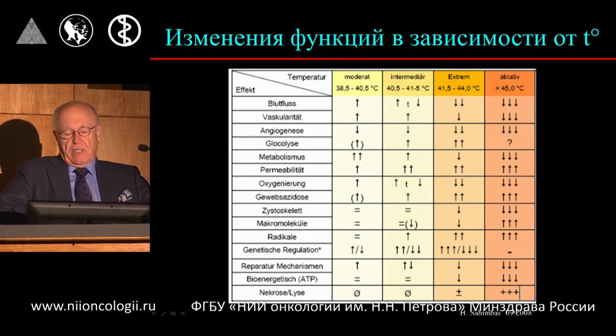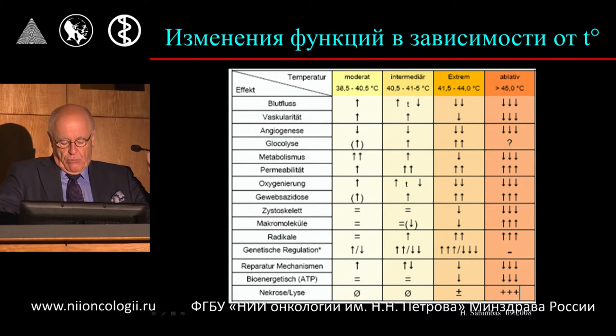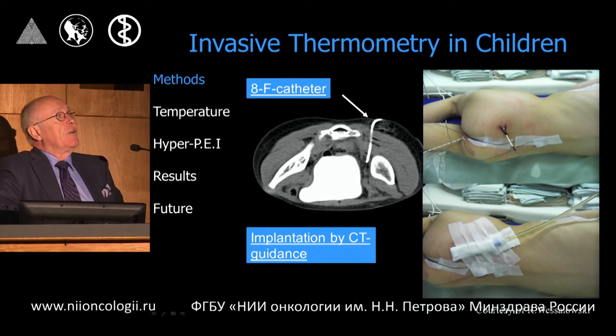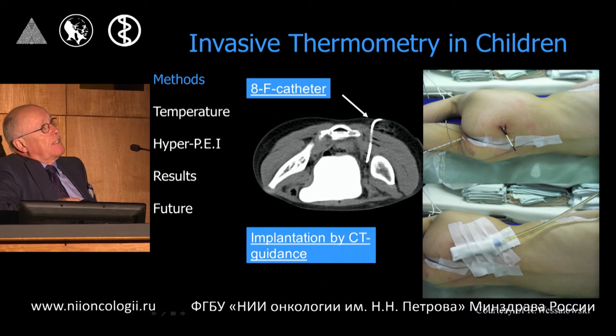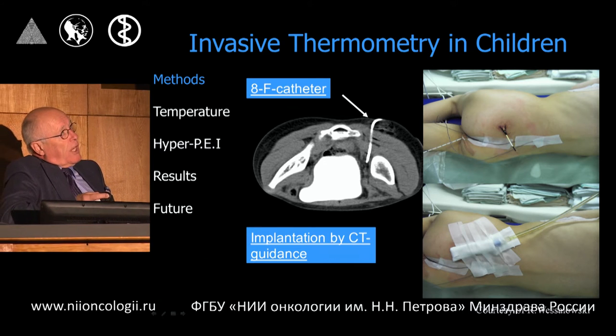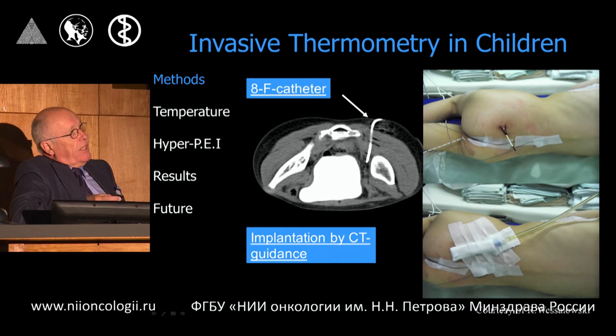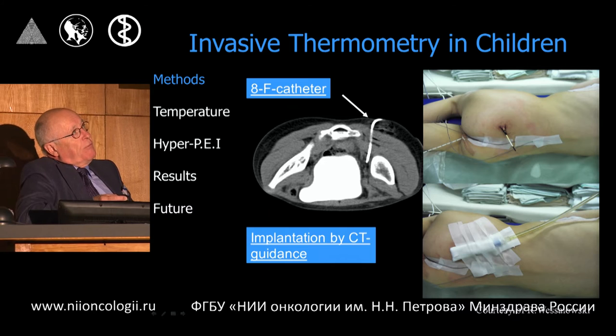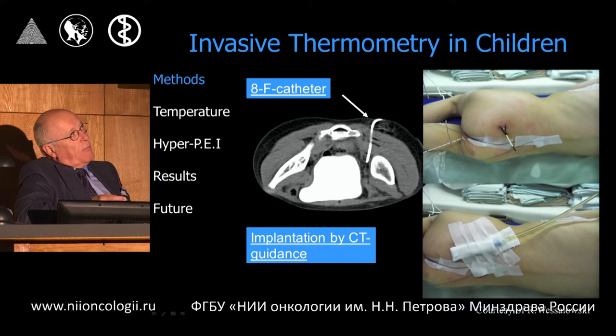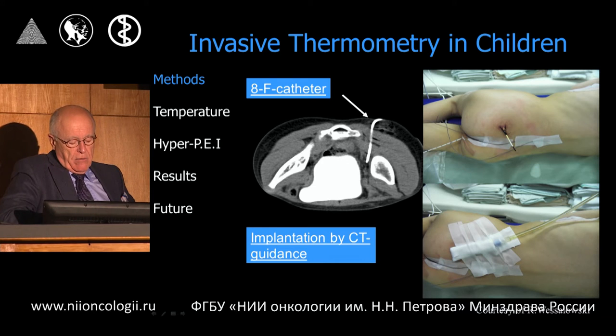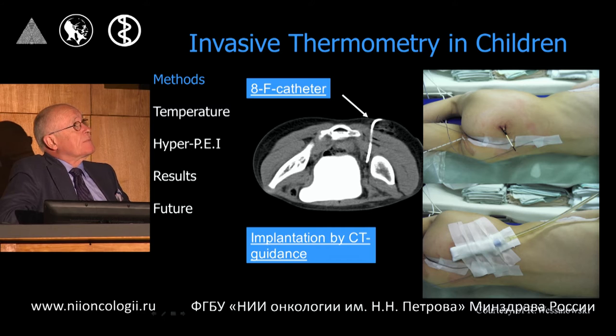This is something we can see, and if we want to deal with hyperthermia on a regular basis, we need to stringently control the temperature inside the tumour. Before, this was done invasively. You can see here a child with a sarcoma where, by means of CT, a device was used to measure temperature inside. But this is an invasive procedure, which is not ideal. Furthermore, with this approach you can only measure temperature in the vicinity of the needle itself — if there is a field of interest some centimetre away, the temperature can be different. It can be lower or higher. Subsequently, this is not an optimal approach to measuring temperature in tissue during regional deep hyperthermia.